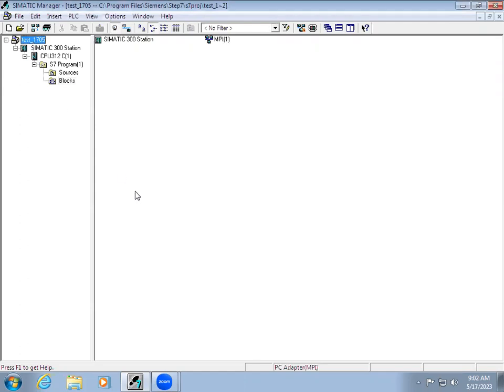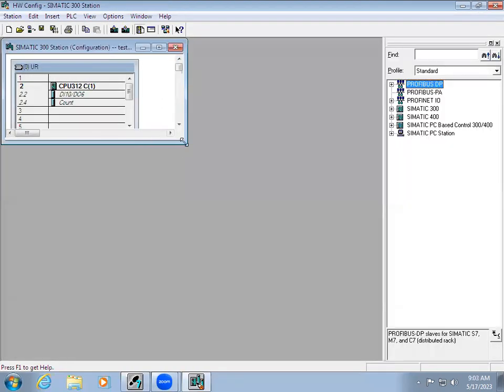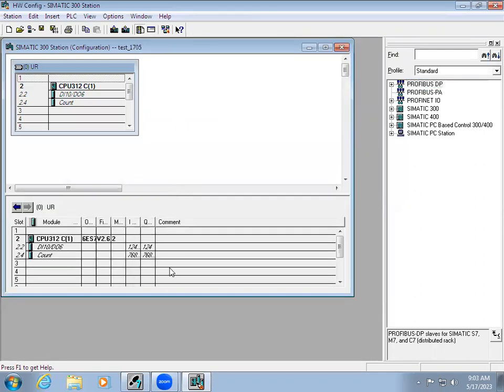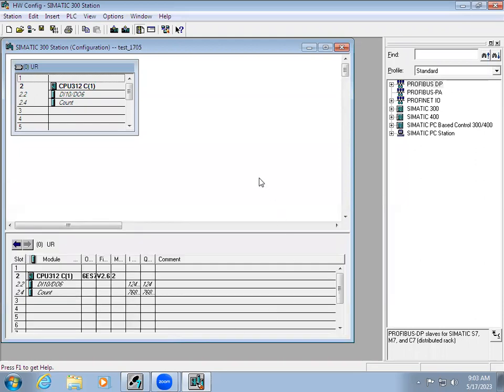The project name is test_1705. I'll go to the Simatic 300 station. Right now I am not going to do a new hardware configuration. Instead, I need to know what logic is present in the controller and what hardware configuration has been done, because sometimes we don't know what modules we have connected or the exact order number. What we can do is upload the logic. If it is an existing controller, the hardware configuration has already been loaded in the controller, so we can upload it and check what addresses are being used for each module.